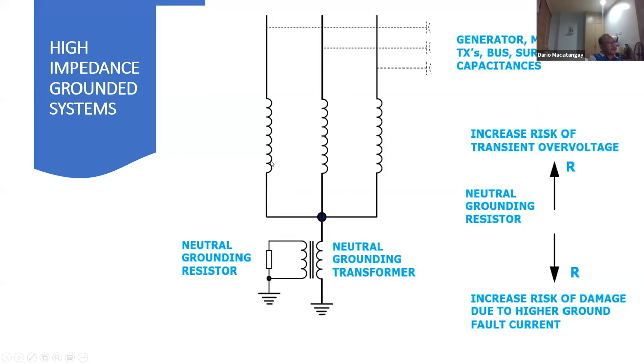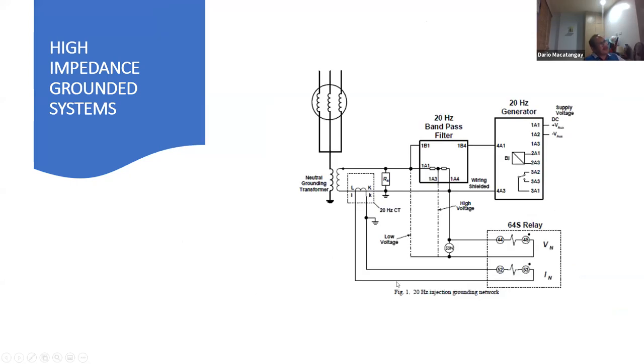So in order to cover this remaining 5%, they have this kind of setup, where they inject a 20 Hertz signal through a bandpass filter and continually inject this 20 Hertz here to the neutral. Now it's using a 64S relay. It's measuring the voltage across the secondary, as well as measuring the current that passes through here. So when there's a ground fault, the response of this band filter is going to change, therefore causing the relay to trip. So that's how they implement the 100% coverage using a 20 Hertz bandpass filter.